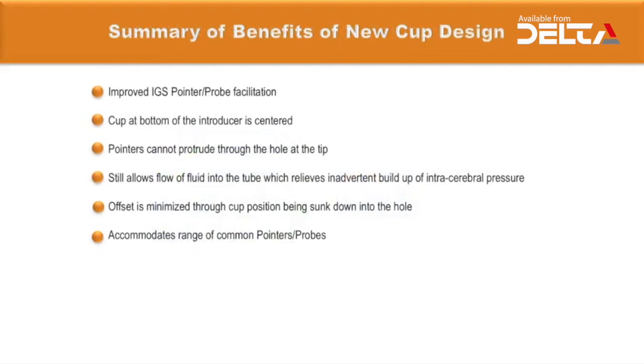The new cup design improves IGS pointer probe facilitation through centering of the cup at the bottom of the introducer. Pointers cannot protrude through the hole at the tip, yet fluid flow into the tube is maintained, relieving inadvertent build-up of intracranial pressure. The offset is minimized through the cup being sunk into the hole, and the design accommodates a range of common pointer probes from different manufacturers.